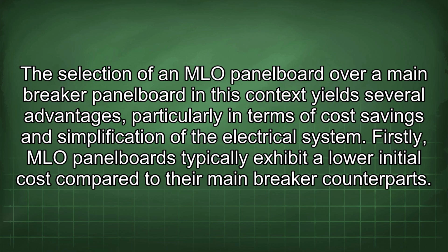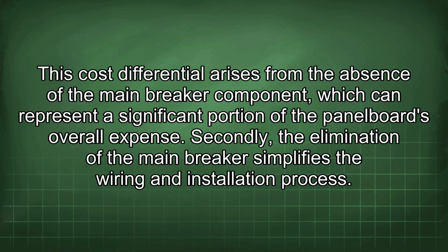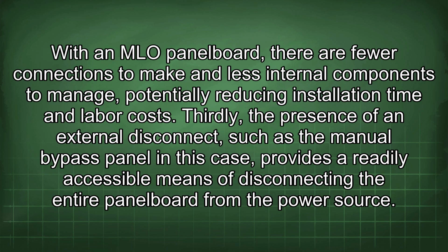Firstly, MLO panel boards typically exhibit a lower initial cost compared to their main breaker counterparts. This cost differential arises from the absence of the main breaker component, which can represent a significant portion of the panel board's overall expense. Secondly, the elimination of the main breaker simplifies the wiring and installation process. With an MLO panel board, there are fewer connections to make and less internal components to manage, potentially reducing installation time and labor costs.